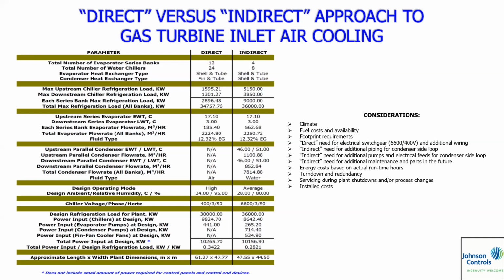Energy costs based on actual runtime hours. All this is at full load. When you got 24 chillers, if you only need 3 operating, last I saw, there's an on-off button. You just turn the other ones off. There is no energy. So really what you got to do is do a full system analysis to see, what's your actual operating profile? How often are you at full load, part load conditions, how many hours, et cetera, and see what your energy consumption is at those points. Then you do your analysis. Okay. Turn down redundancy plays into that. Servicing during plant shutdowns, installed cost. Okay. When you start doing all that stuff, these guys won that particular analysis in this case, believe it or not.